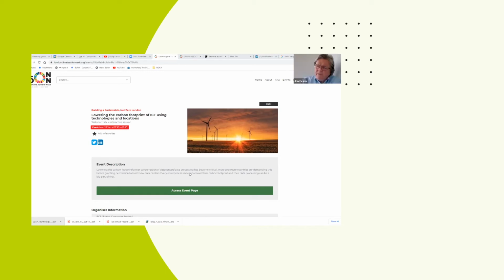Can I come in here with my plug for immersion cooling, another passion of mine? In that instance, you disconnect the fans on the servers to immerse them in a non-conductive liquid bath. By disconnecting the fans, you reduce the power demand by 10 to 15%, which is how much power the fans take to cool the servers. The actual power needed to run the immersion cooling solution is only that 10 to 15%, and the rest of the H&V load disappears.